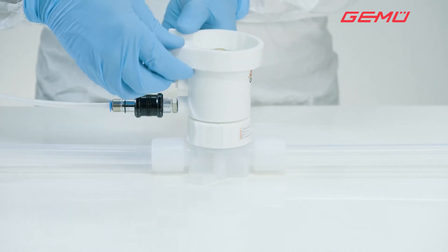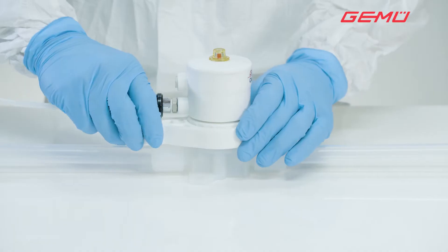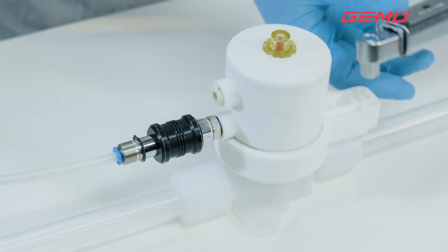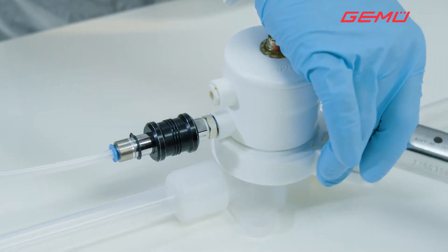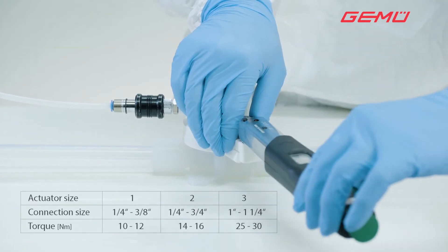Position the actuator on the body and tighten the central nut clockwise until it is hand tight. Position the GEMÜ service tool in the correct position on the central nut, and attach the torque wrench in the extension for the service tool handle. Failure to do so will result in an incorrect torque. Tighten the central nut to the specified torque.